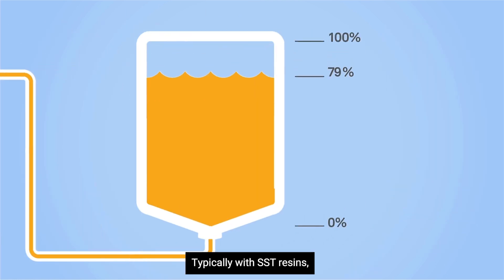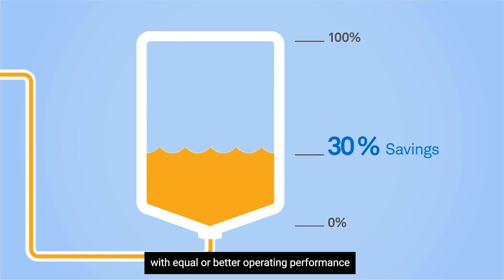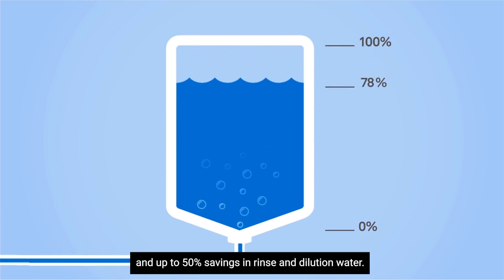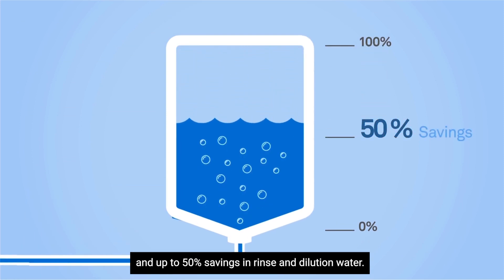Typically, with SST resins, you save 20-30% on regeneration chemicals with equal or better operating performance, and up to 50% savings in rinse and dilution water.